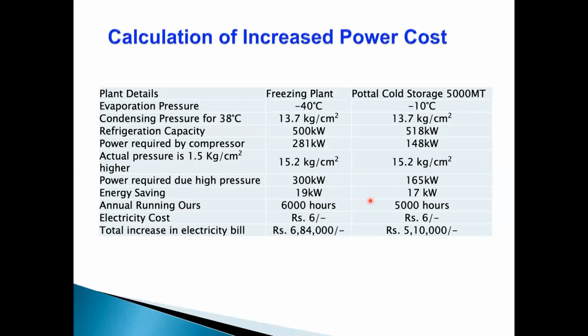This is a calculation showing actual results obtained from a -40 freezing plant at 500 kilowatt. I'll not go into detail. If you have 1.5 kg pressure extra over the design pressure, then you save around 6,85,000 rupees. It's almost $10,000 in a year. Sorry, now the rate has gone up, so it can be around $9,000. And for a potato cold storage operating at -10 degrees centigrade, it saves you around 5 lakh rupees, or around 6,000 to 7,000 US dollars. So if you consider a good product, the payback period can be less than a year.